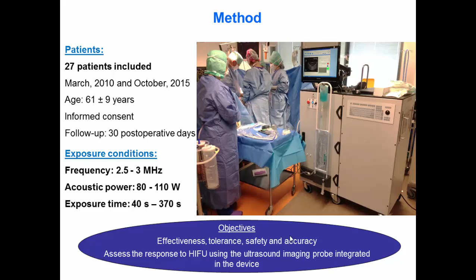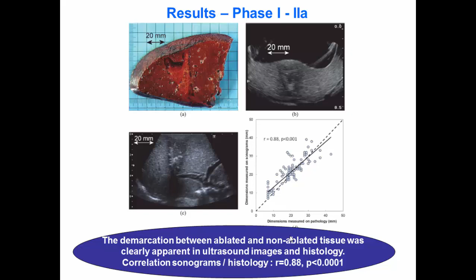These are the results of the first phase. So we confirm that we can ablate a large region of the liver in a short amount of time. And importantly, and it is a huge difference when compared with the spherical transducer, we observed that we can clearly identify the lesion on the ultrasound images. So this is with the probe integrated in the device, and this image was obtained with a higher frequency ultrasound imaging probe. And we observed a close correlation between what was observed in ultrasound images and what was observed in gross pathology, with a high correlation coefficient.